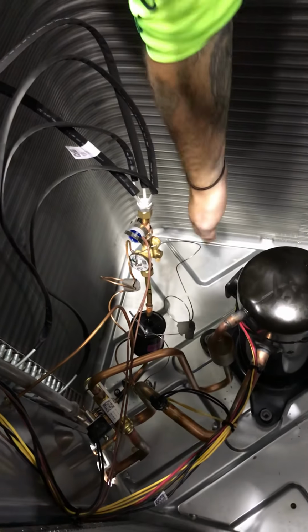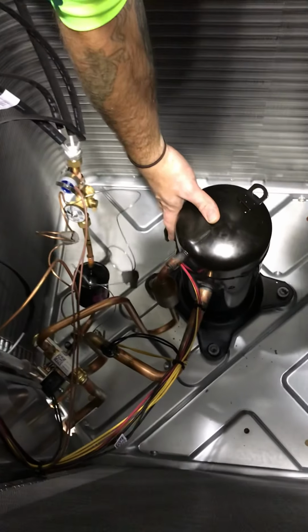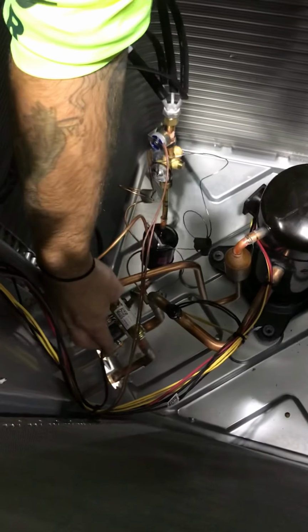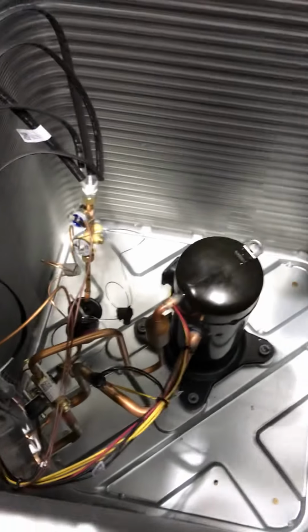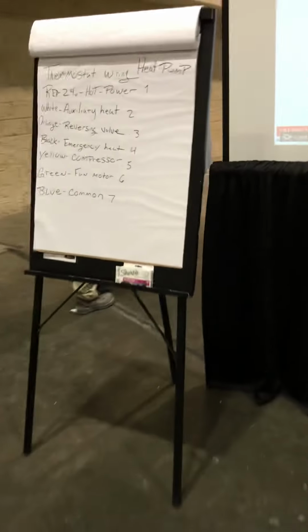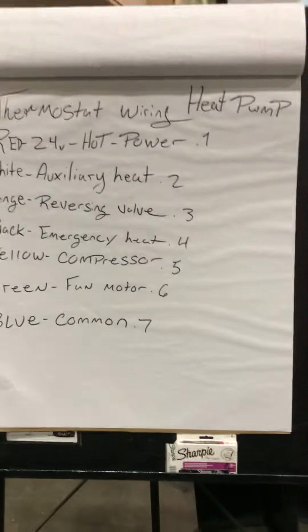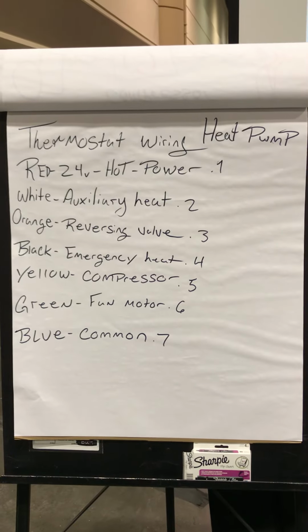Other than that, you have your junction, which we already talked about. This is for your reversing valve. That's all there is to it, guys. And those are all pressure sensors, they don't go bad. And this is a complicated version of HVAC, okay? So if you understand this, a straight cool is very simple because you're not dealing with the reversing valve and the heat pump.